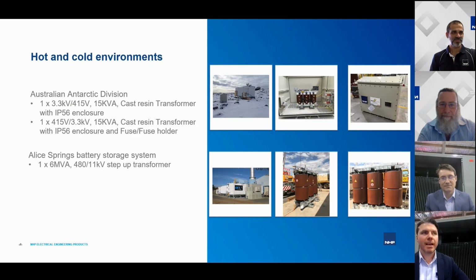What were some of the considerations and challenges that had to be addressed in order to supply this infrastructure down there? Yeah, there certainly were challenges, and the challenge there is the negative temperatures that can go below -40 and -50. The cast resin transformers were designed and tested to class C2, which is -25. So it is pretty cold, but maybe still not good enough to install outside in Antarctica. Therefore, we installed a resistive heater inside the IP56 sealed enclosure, and that maintains a reasonable temperature for this transformer.